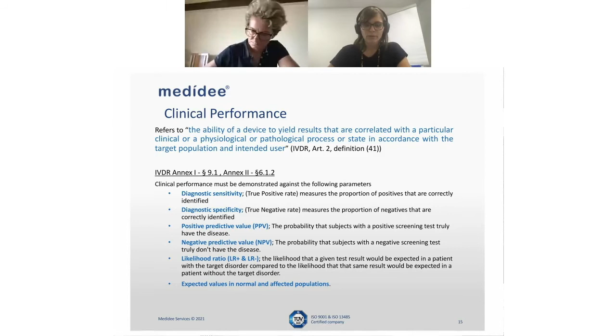And these are, for example, the diagnostic sensitivity, so the true positive rate of a device, diagnostic specificity, the positive predictive value, the negative predictive value, the likelihood ratio, and the expected value in normal and affected population. So these are all aspects to be considered as part of a demonstration of the clinical performance of an IVD medical device. And these now need to be assessed within a clinical setting, so using a clinical sample as relevant to the intended use of the device.